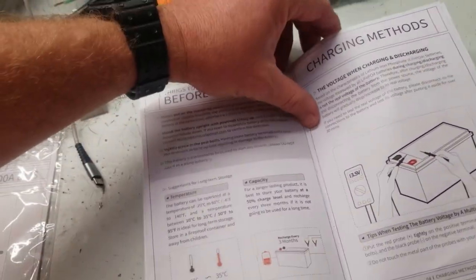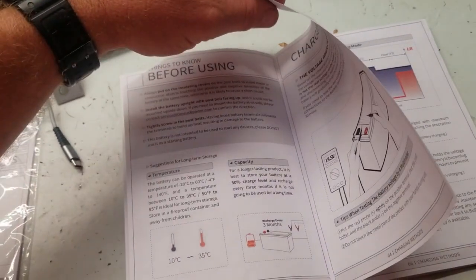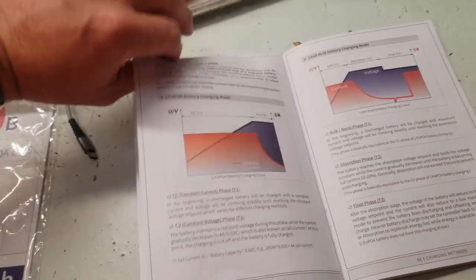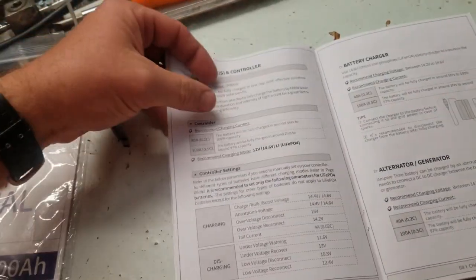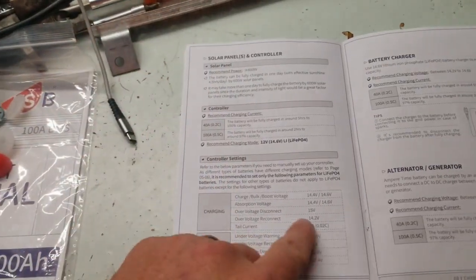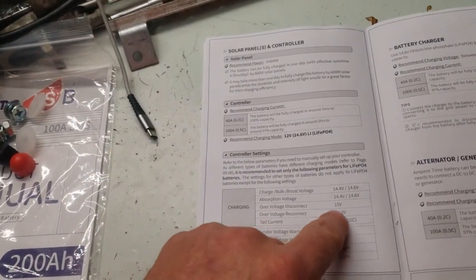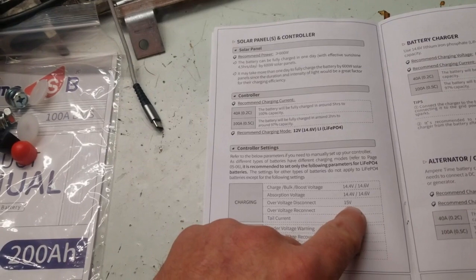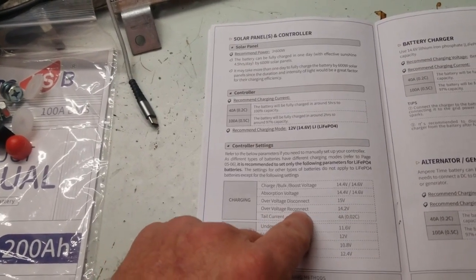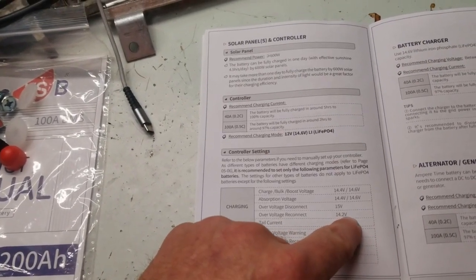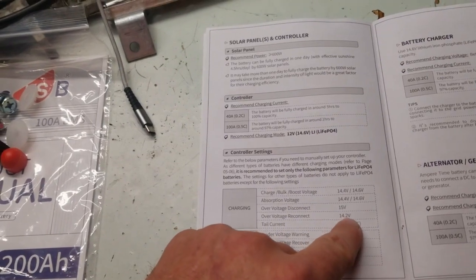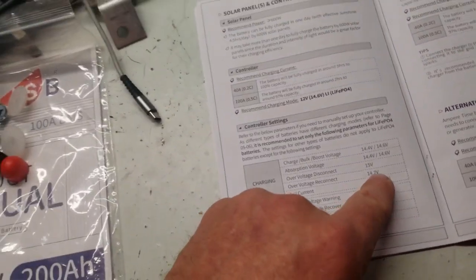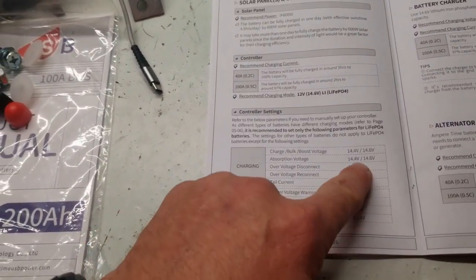I think I saw it. There's 15 volts where the high volt disconnect will shut off. Here it is — over voltage disconnect, 15 volts, it will shut down. And over voltage reconnect is at 14.2. So the voltage has to come down to 14.2 before you can get any juice out of it.